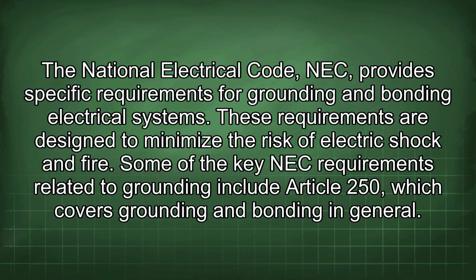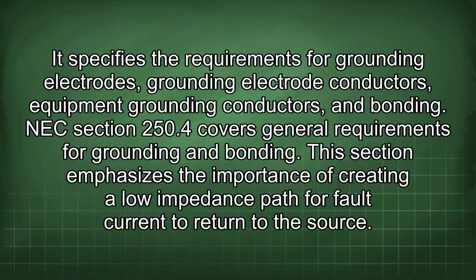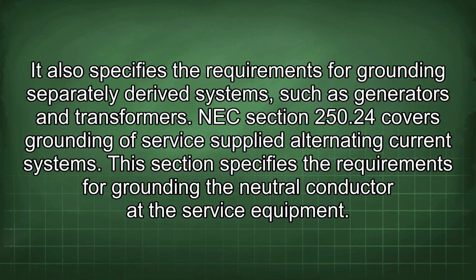The National Electrical Code, NEC, provides specific requirements for grounding and bonding electrical systems. These requirements are designed to minimize the risk of electric shock and fire. Some of the key NEC requirements related to grounding include Article 250, which covers grounding and bonding in general. It specifies the requirements for grounding electrodes, grounding electrode conductors, equipment grounding conductors, and bonding. NEC Section 250.4 covers general requirements for grounding and bonding. This section emphasizes the importance of creating a low impedance path for fault current to return to the source. It also specifies the requirements for grounding separately derived systems, such as generators and transformers.